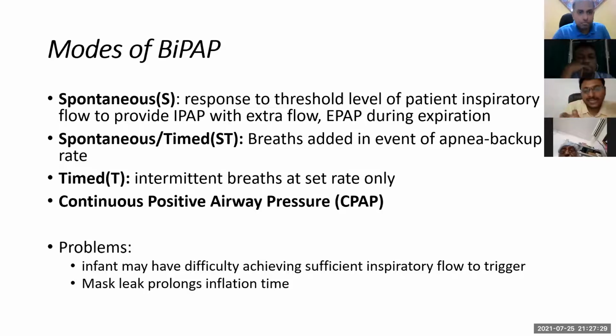How does the machine recognize? When the patient tries to breathe, he will draw some air from the circuit into his lungs. So there will be a negative pressure. That will trigger the machine, and the machine will now give the set amount of pressure. So pressure has been set. The IPAP you have set. Suppose you set a pressure of 10. So 10 centimeters of water pressure will be delivered from the machine through the interface to the patient's lung. So that is called IPAP. So in spontaneous mode, the patient has to trigger the machine, has to tell the machine that I want to breathe. But the work does not have to be done by the patient. The machine will give the positive pressure to the patient to breathe and have the tidal volume.